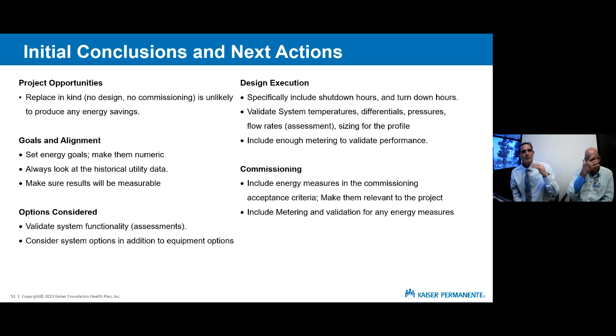And then for some of these projects, whether boilers or chillers - Sandy mentioned the chiller where we'll call it a failure, where we didn't map the kW point. It's really important: if you're going to set a kW per ton goal, you've got to map the kW point. If you're going to do a boiler efficiency goal, you've got to put the gas meter upstream of the boiler. So make sure in design we include enough metering, or some logical way, that we're going to come back and validate that performance later on.